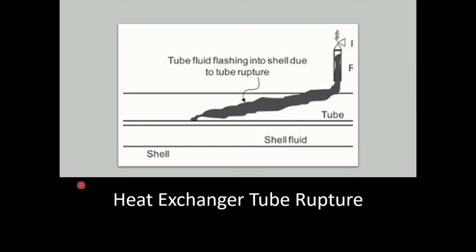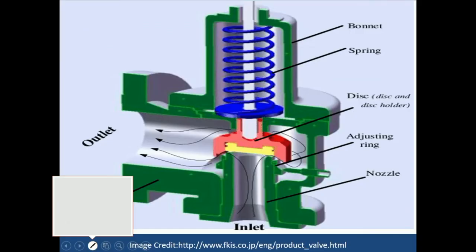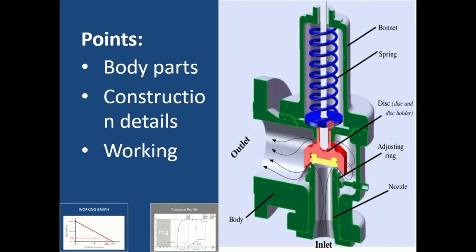Another cause is cooling system failure — a typical example in any chemical plant where cooling system failure causes the temperature to rise exponentially, which can be a problem. Now let's look at a cut view of a pressure safety valve. The bonnet is the outer structure and should be strong enough to bear any mechanical vibration. A spring is attached and plays a vital role in the safety valve because the spring tension is adjusted depending upon the set point.